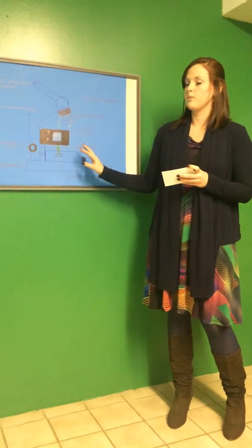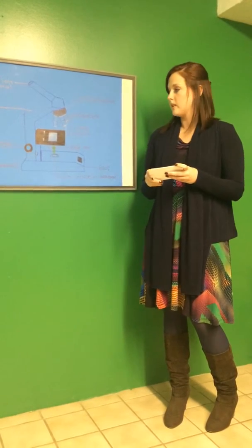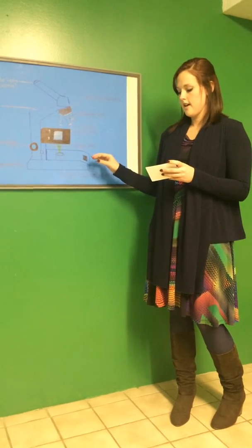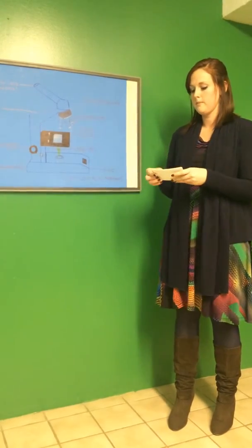In order to clean your microscope, you're going to make sure that you clean the ocular lenses and the objective lenses with nothing except lens wipes. The rest of the microscope, including the stage, can be cleaned with just a soft paper towel or cloth. Turn your microscope off and allow it to cool completely, then recover it and put it away. When you're putting it away, be sure that you carry it correctly. You're going to want to carry it with one hand on the arm, which is right here, and the other hand on the base, which is right here.